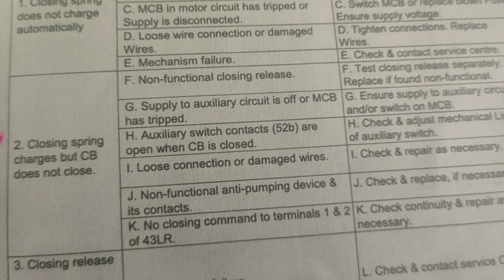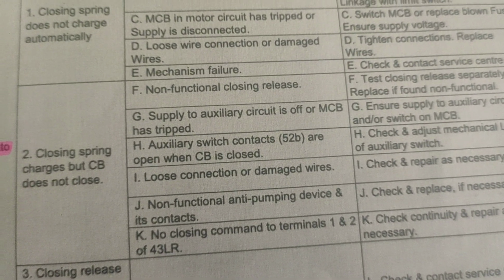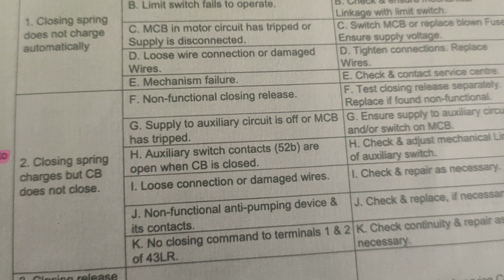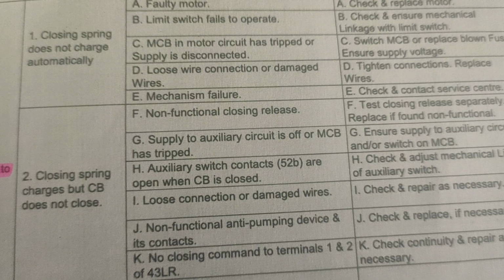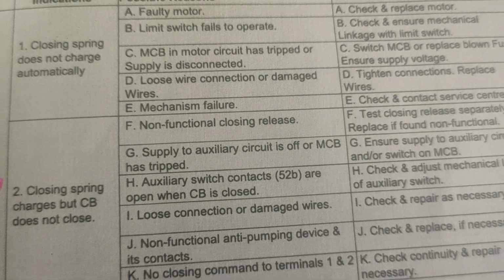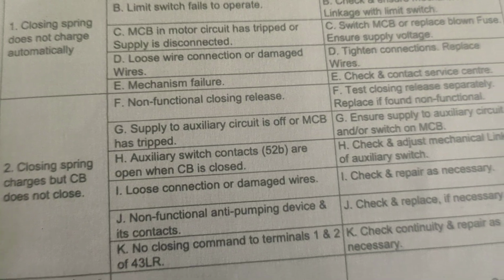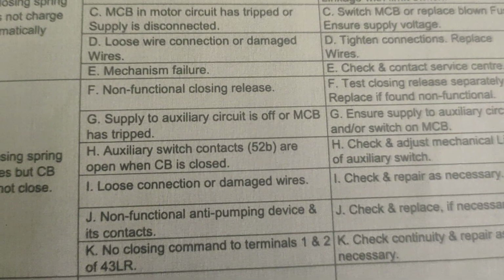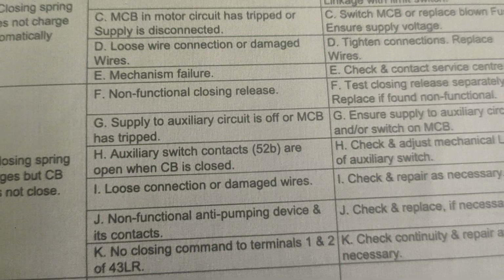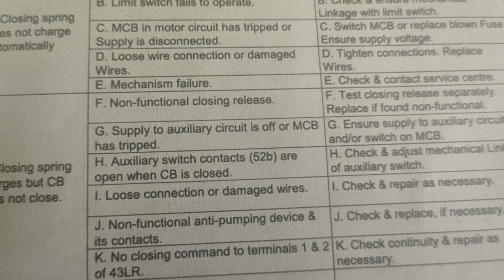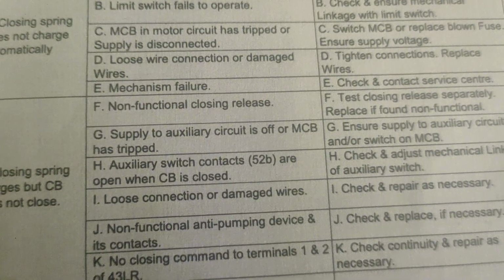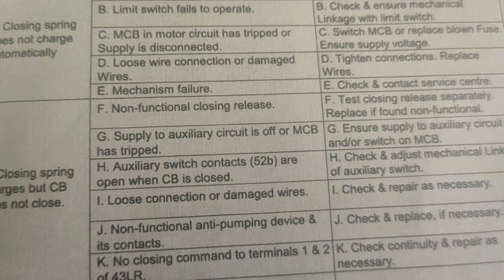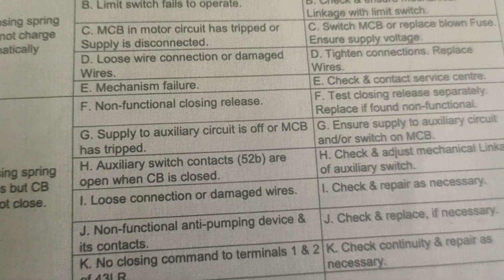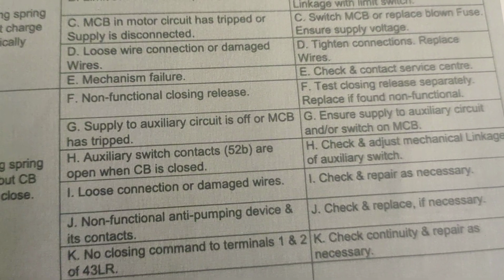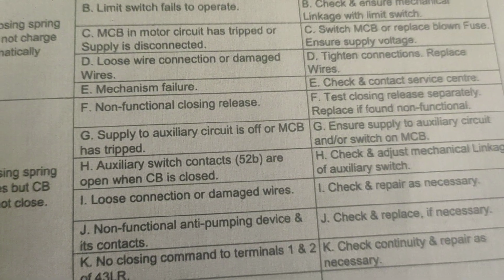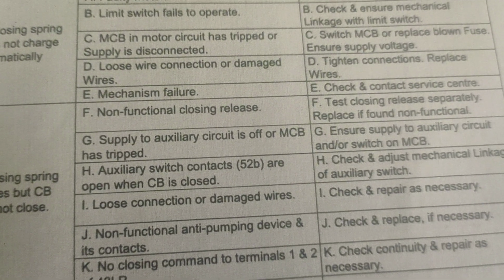Also, the closing spring is charged but the circuit breaker does not close. Here the closing spring has no problem. The MCB is in good condition, the limit switch is in good condition, there are no faulty motors and no mechanism failures, but other functions are involved. The closing release may be non-functional, so test the closing release separately and replace it if found non-functional. Here the supply to the auxiliary circuit is off or the MCB has tripped, so ensure the supply to the auxiliary circuit and switch on the MCB. Auxiliary switch contact 52b is open when the circuit breaker is closed.